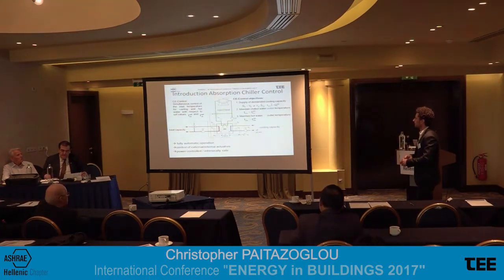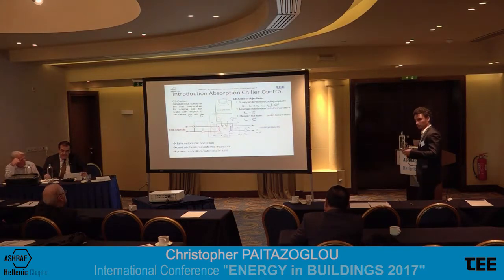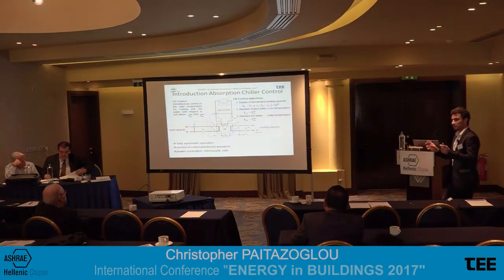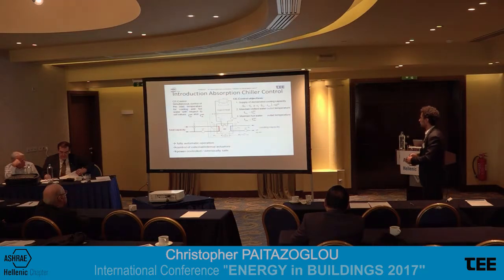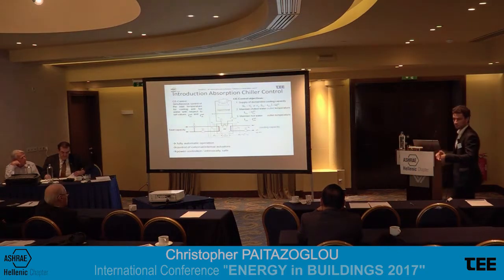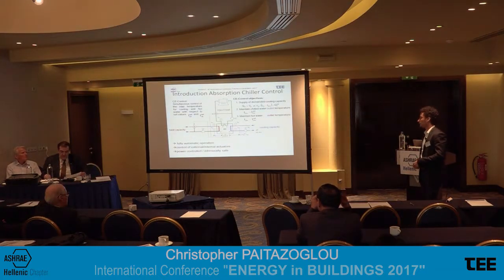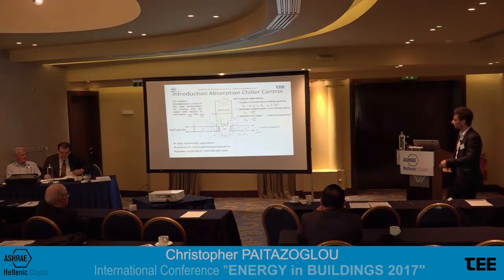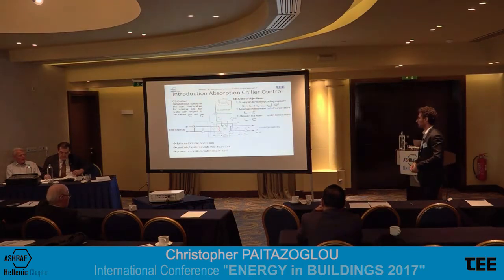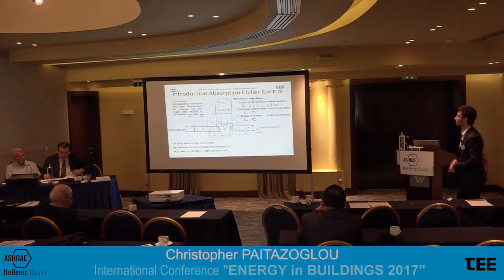So the inlet temperatures of the dissolver and the absorber are set values that are regulated simultaneously in order to provide the cooling load, in order to cover the output temperature here at the evaporator, and also sometimes, especially for CHP systems, provide a certain output temperature at the dissolver so that the CHP system is not shutting down. The chillers are fully automatic, and they are autonomously controlling their internal and external actuators, all the actuators that you can see here, and it's power controlled and intrinsically safe.